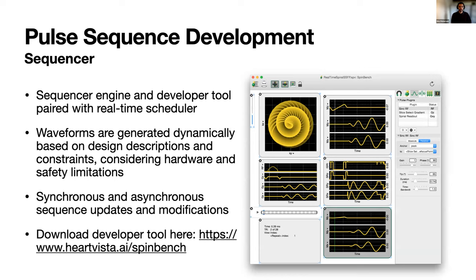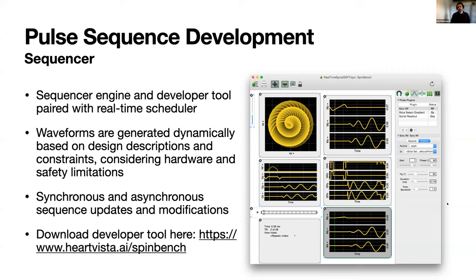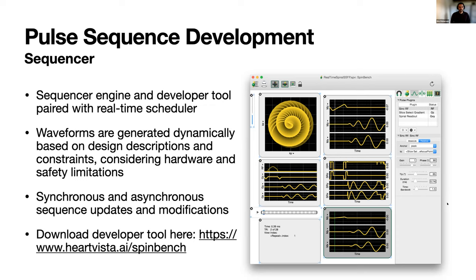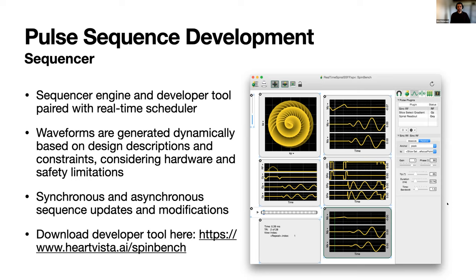The pulse sequence development is done in SpinBench. This is really a sequencing engine developer tool and a scheduler. You can actually download this—the last bullet there gives you the link. You can download the UI, it's a Mac UI. That's how we design our pulse sequences. In the library side, we can do some of the sequencing. Once you've designed these waveforms, they are generated dynamically as we scan based on the design that you gave but also hardware limitations, safety constraints, things like that on the system that you're running on. This also allows for synchronous and asynchronous updates and modifications to the pulse sequence while you're running.